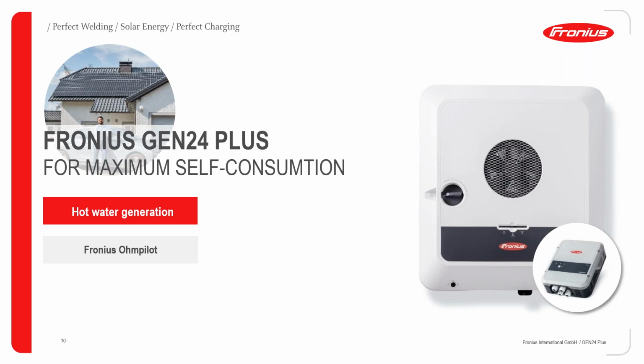We can even integrate it into our heating system if we want to. With this heating rod in the boiler and this maximizing of self-consumption, we have a very efficient way to store our surplus energy. We increase our own consumption, we are not feeding into the grid, and we use it at a later stage when the customer comes home at night — he can then shower, taking the hot water back again.